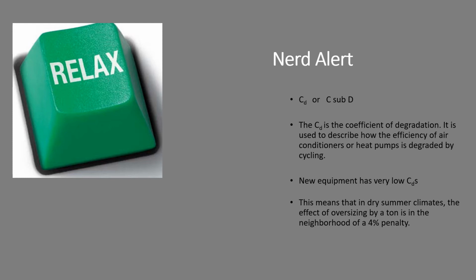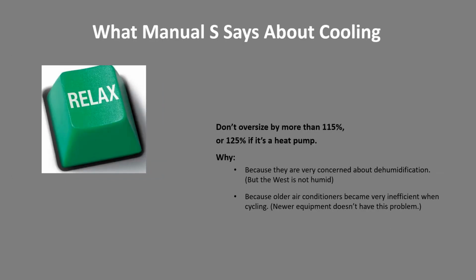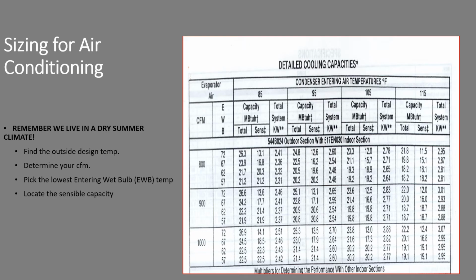A good estimate is that oversizing an air conditioner in the summer by a ton might only get you a penalty of 4% on energy efficiency. I'm not advocating oversizing. Again, Manual S says don't oversize. Why? Because they are quite concerned about dehumidification.